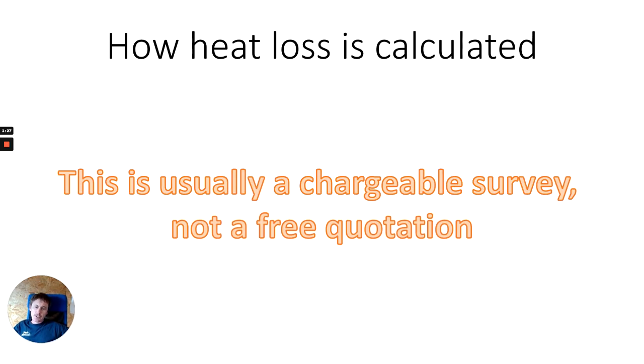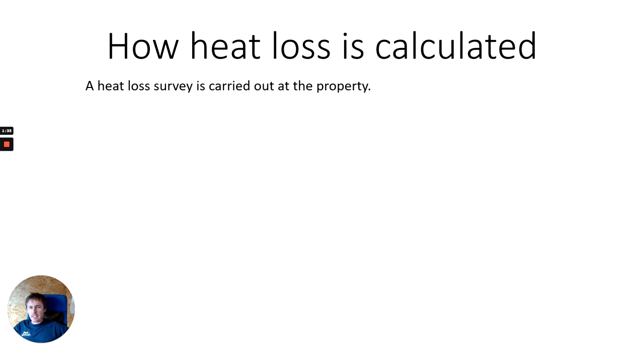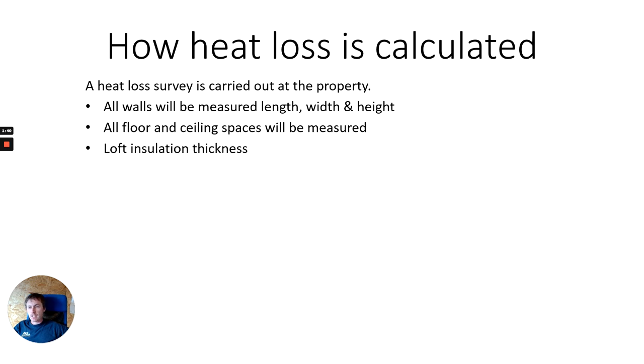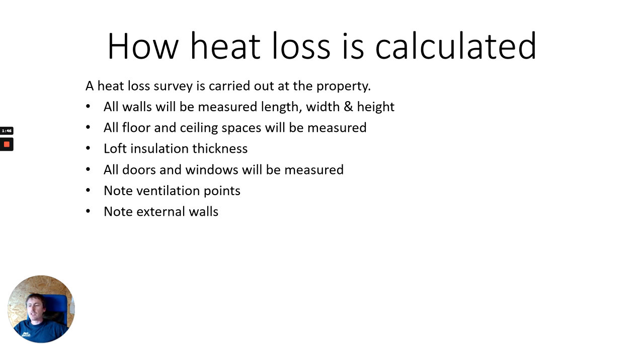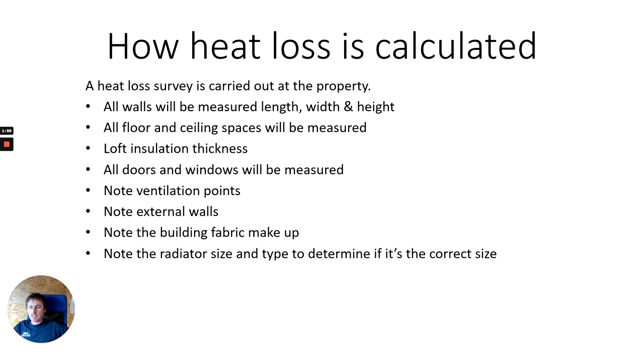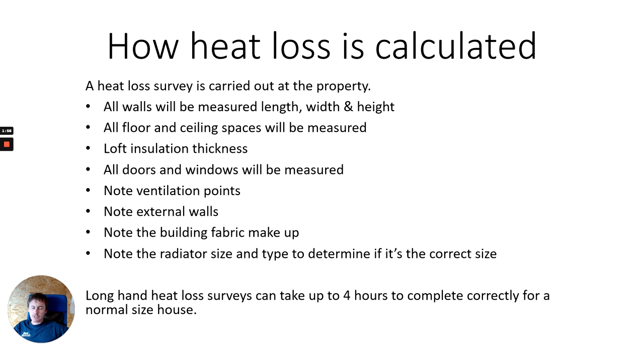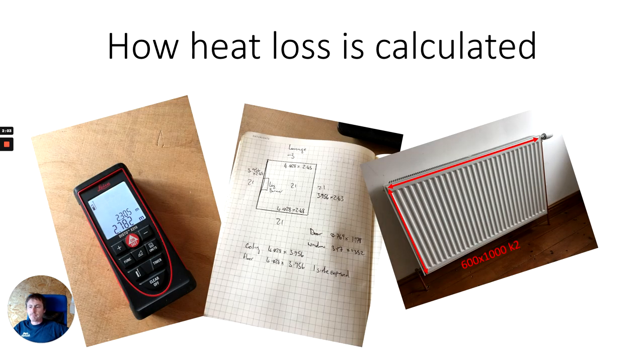A heat loss survey is usually a chargeable survey, not a free quotation. All walls, lengths, widths and heights are measured; all floors and ceiling spaces are measured; loft insulation thickness is recorded; all doors and windows are measured; we note ventilation points, external walls, building fabric makeup, and we note radiator size and type to determine if it's the correct size. Long-hand heat loss surveys can take upwards of four hours to complete on-site for a normal-sized house. We'll measure everything, make rough guides, and measure all your radiators so we can go back and calculate if they're actually the right size.